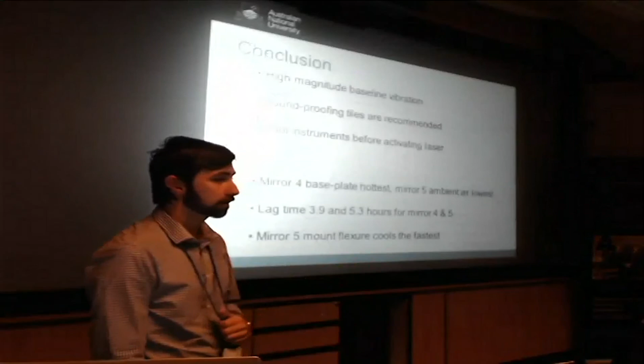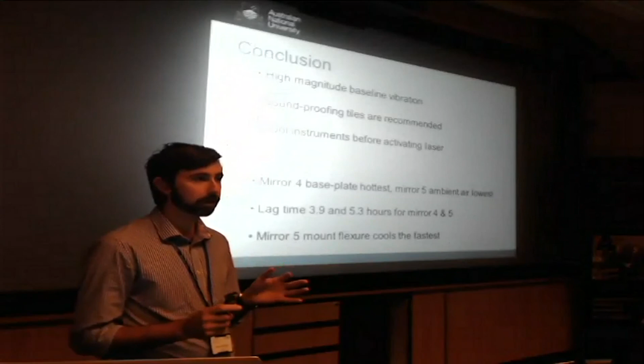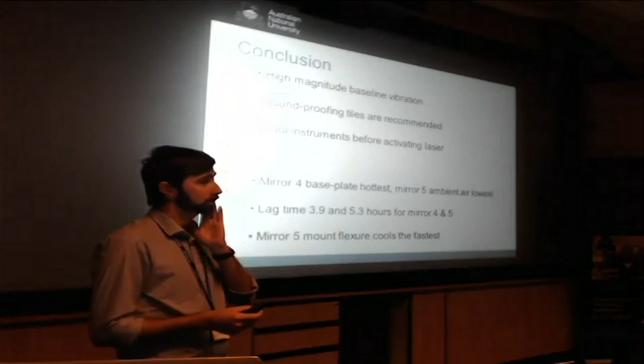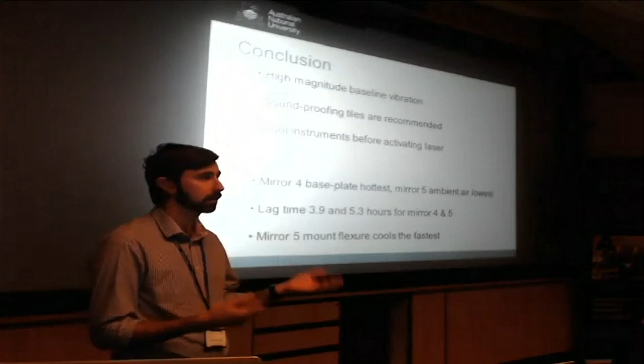Okay, so to wrap all that up, we detected possibly problematic vibration between 0 and 150 Hertz. The telescope baseline vibration may impair laser functionality. We'd recommend that soundproofing tiles be affixed to the laser enclosure in order to damp any disturbing acoustic inputs. We'd also recommend that all the instrumentation is allowed to sufficiently cool before the lasers are activated. And all of the thermal data is going to be passed on to EOS to aid in their continuing investigation. So thanks very much. We'd just like to make some acknowledgements, and that's it.